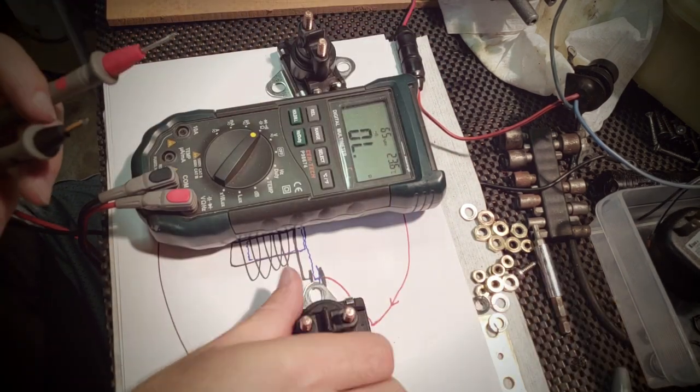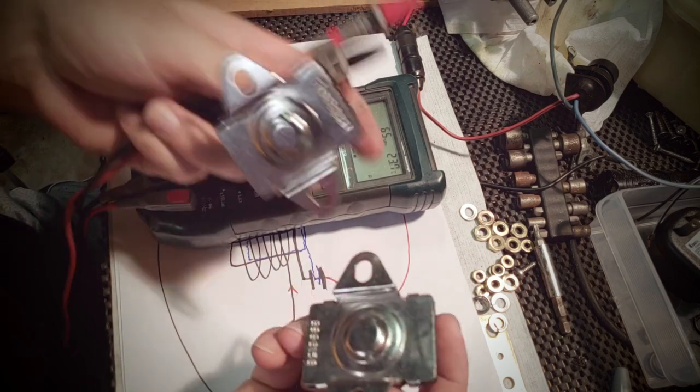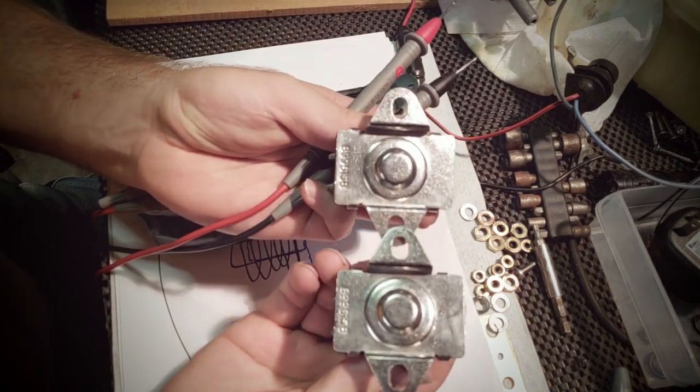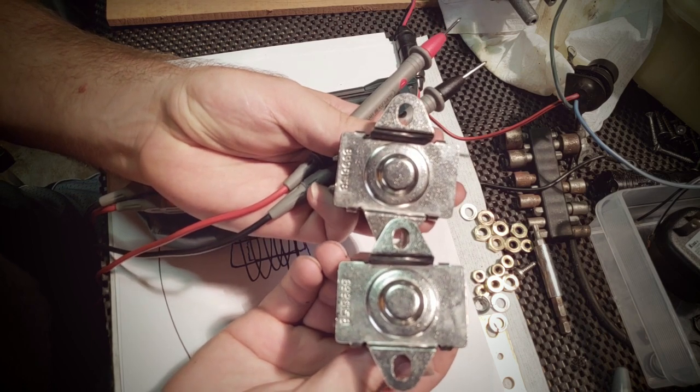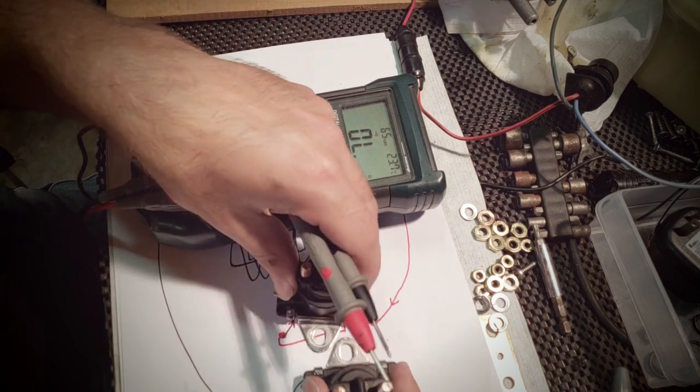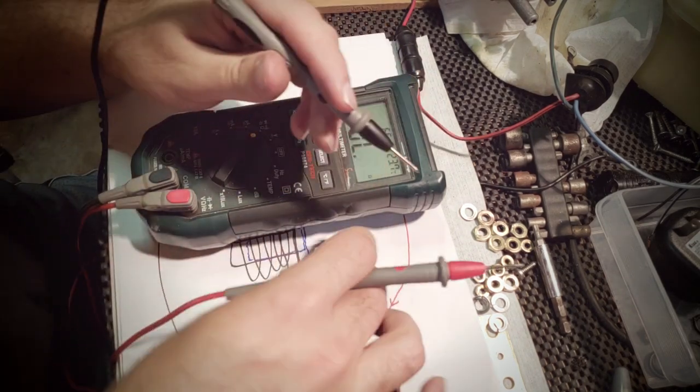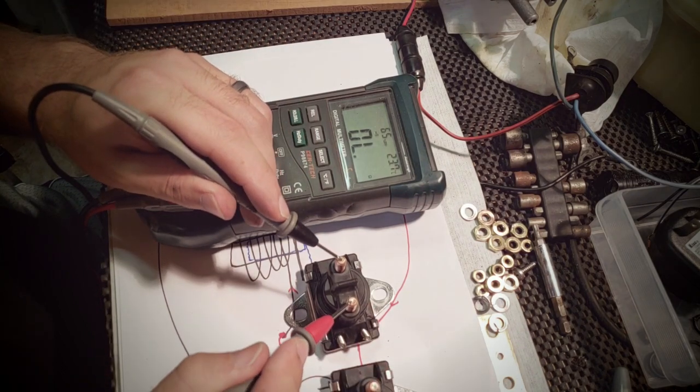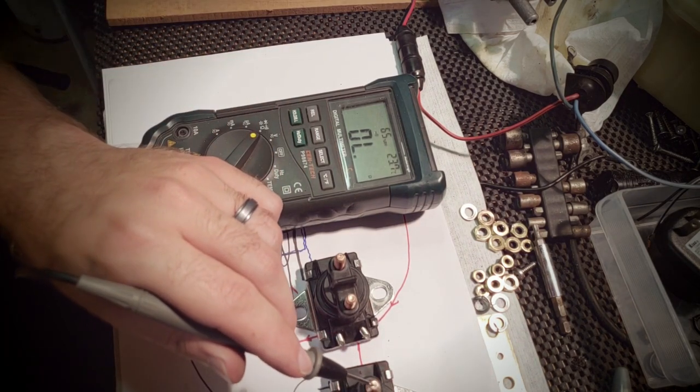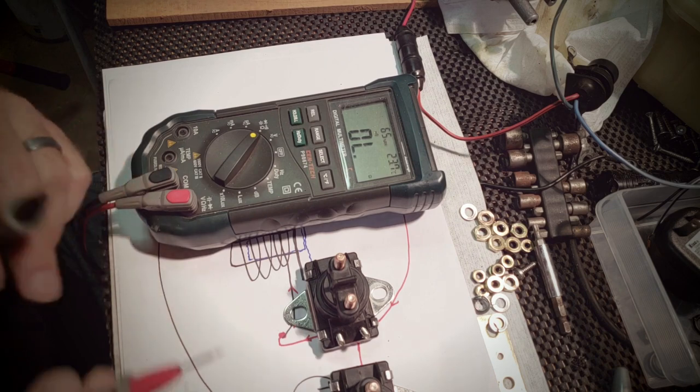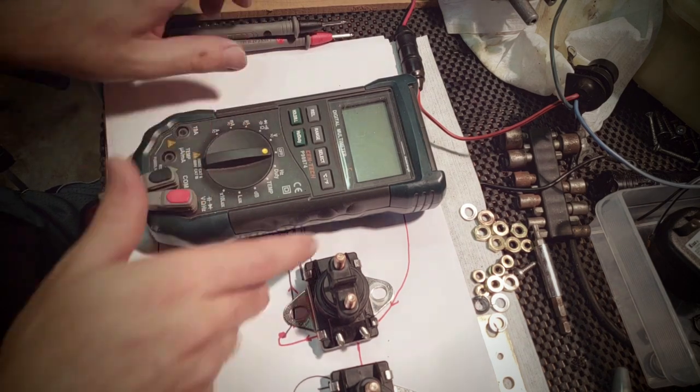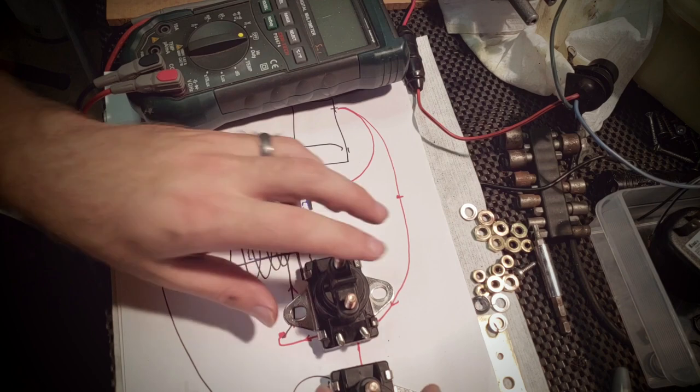Let's check the other one. And I will mention that if you actually look at the underside of these, they're actually exactly the same part. The ID number is the same, which makes sense. It's just a relay. So same thing. Now, I don't remember which one I already checked. So I'll just check them both. No continuity. No continuity. Good.